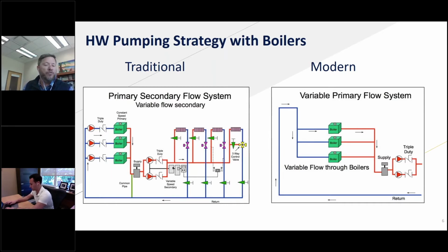That drove divorcing the two systems and essentially dedicating constant pumps to the boilers, and then allowing the secondary pumps to pump the system and putting those on variable speed drives, thus allowing us to start saving energy by only pumping the amount of water that we needed in the secondary loop. As time has moved on and as development has happened not only with chillers but also with boilers, we've had the advent of the ability to vary flow within an operating unit.